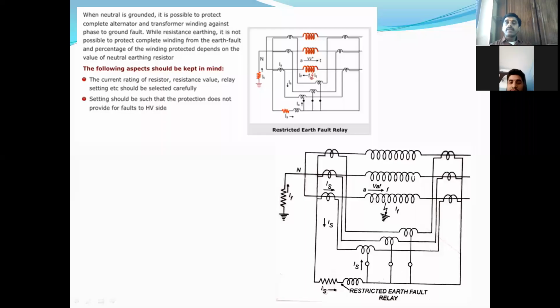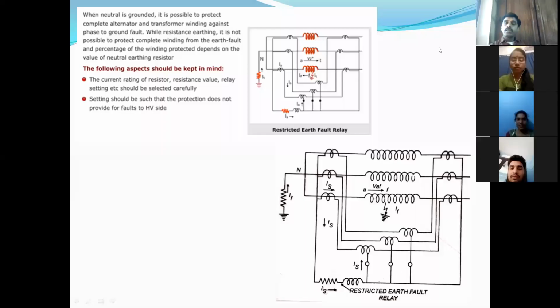Yeah, thank you for joining again. We are continuing with the restricted earth fault protection. We have already discussed that when the neutral is grounded, it is possible to protect the complete alternator transformer winding against phase to ground fault.